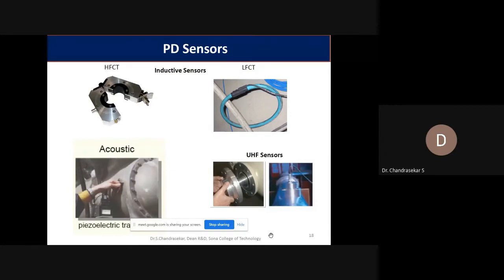Now we are coming to the sensors, the partial discharge sensors commonly used for high voltage measurements. I hope you now understand what high voltage is, and the importance of monitoring insulation systems in high voltage. If there is any failure in the insulation system, it will lead to a major economic loss and also a complete shutdown of power. Therefore, as preventive maintenance work, nowadays all electrical utilities give much preference to understanding the technologies for high voltage sensors.